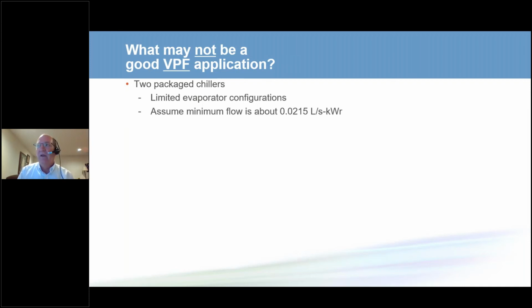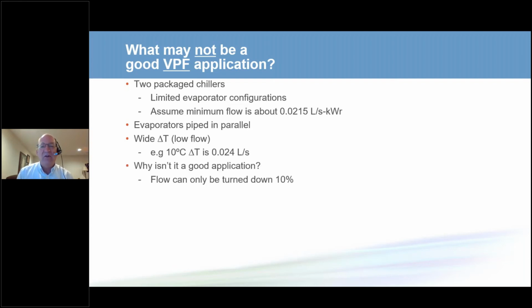So in this case, the minimum flow rate is about 0.02 liters per second per kilowatt of refrigeration. The chillers are piped in parallel, and the designer is using a 10 degrees C delta T, 18 degrees Fahrenheit. At 10 degrees C, that flow rate is 0.024 liters per second per kilowatt. Well, that means that we can't turn the flow down more than 10%. So this isn't a good variable primary flow option. What could we do in this case?